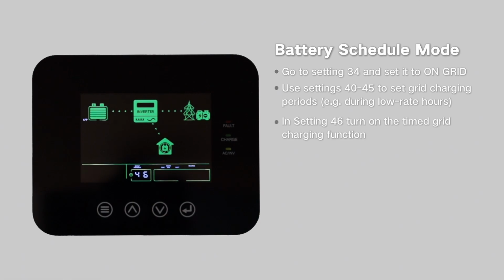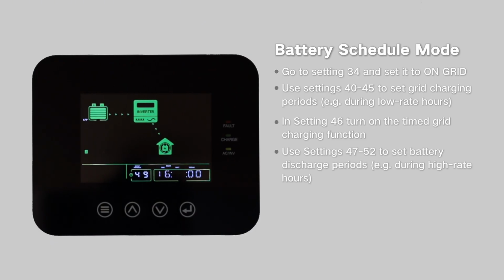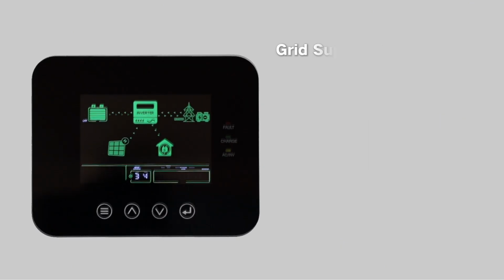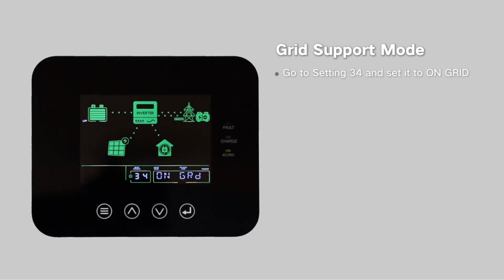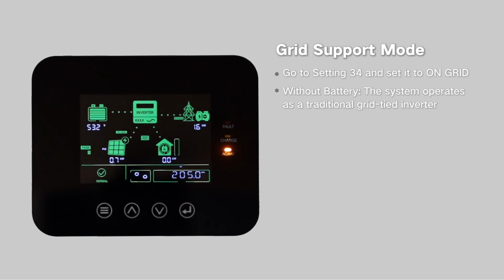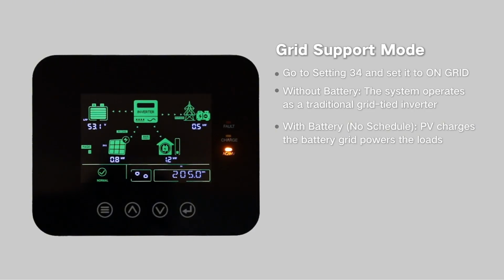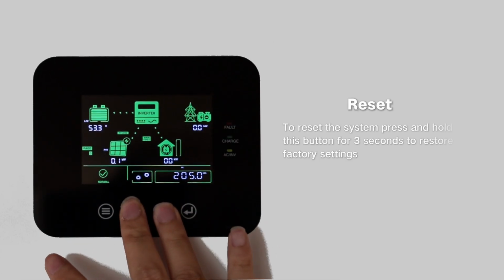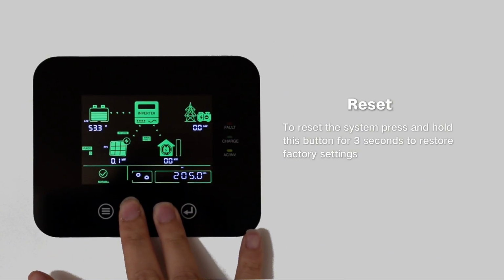In setting 46, turn on the timed grid charging function. Use settings 47 to 52 to set battery discharge periods. In setting 53, turn on the timed battery discharge function. Grid support mode. Go to setting 34 and set it to on grid. Without battery, the system operates as a traditional grid-tied inverter. With battery, no schedule. PV charges the battery. Grid powers the loads. Reset. To reset the system, press and hold this button for 3 seconds to restore factory settings.